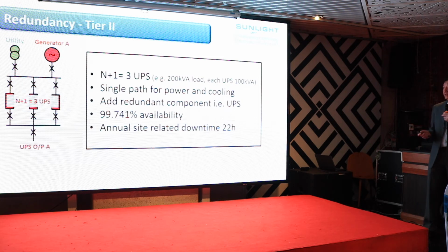If you talk about the redundancy for Tier 2, we talk about the N plus 1. Here you have 3 UPS now. Each will be 100 kVA. So in short, whatever it is, one of the UPS will be made redundant. So you actually add a redundant component, UPS. That increases your availability, 99.741%, and cuts down your downtime to 22 hours.